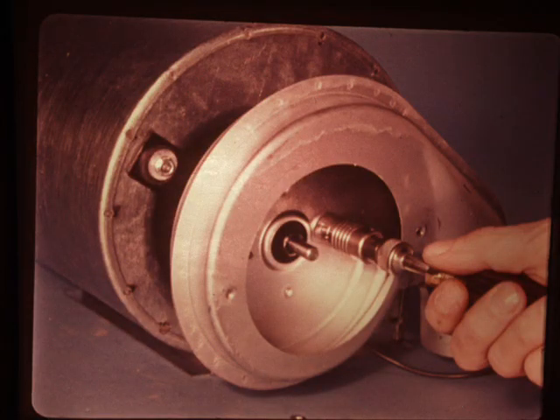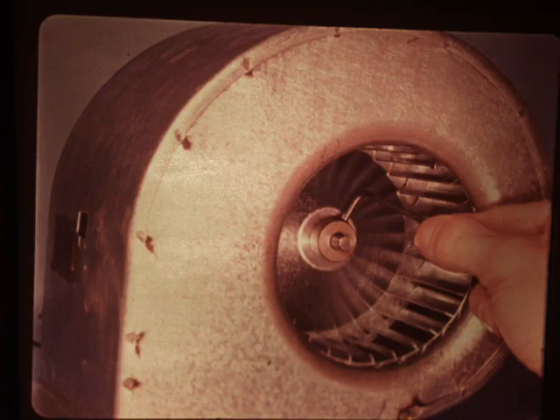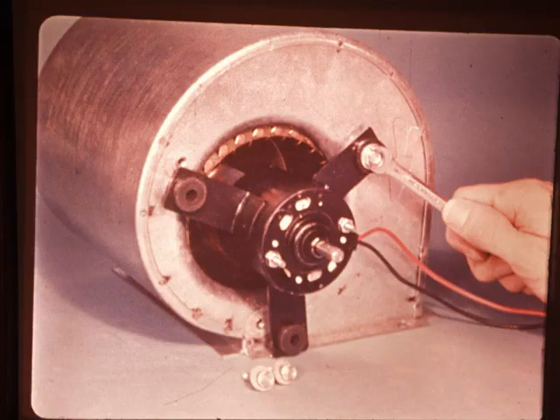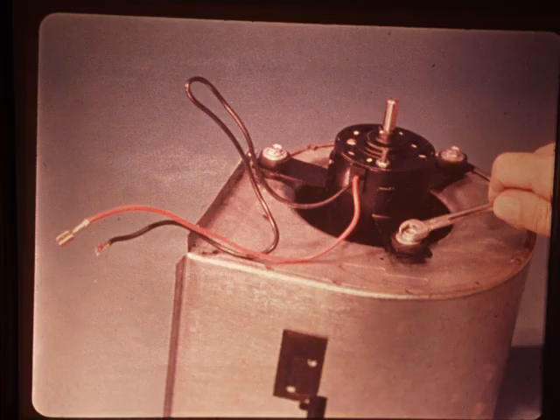2 nuts retain the inner housing to the blower motor. Loosen the recirculating air blower wheel with an 1/8" Allen wrench. Remove 3 retaining screws to allow removal of the motor. The motor, incidentally, is sealed and requires no periodic lubrication. With the motor removed, you can then take the recirculating air blower wheel out of the housing.